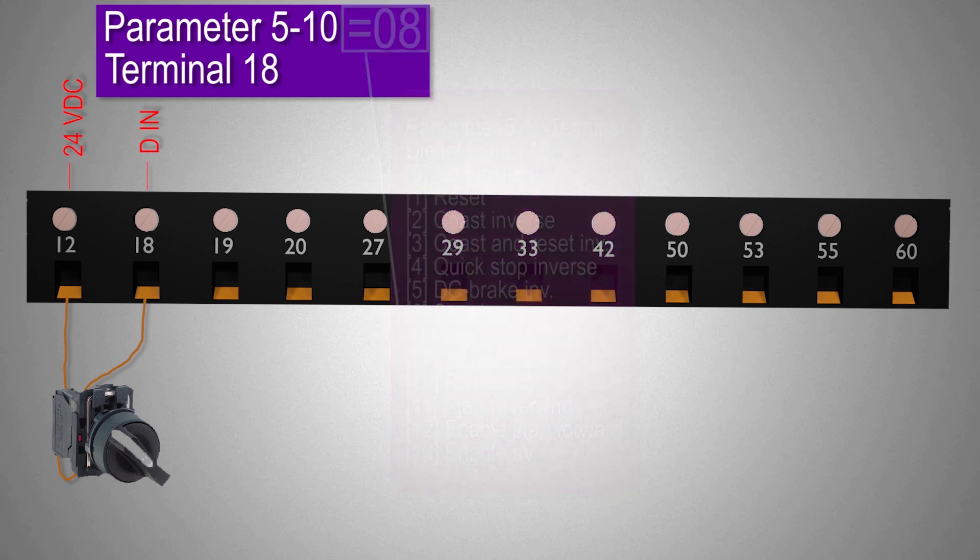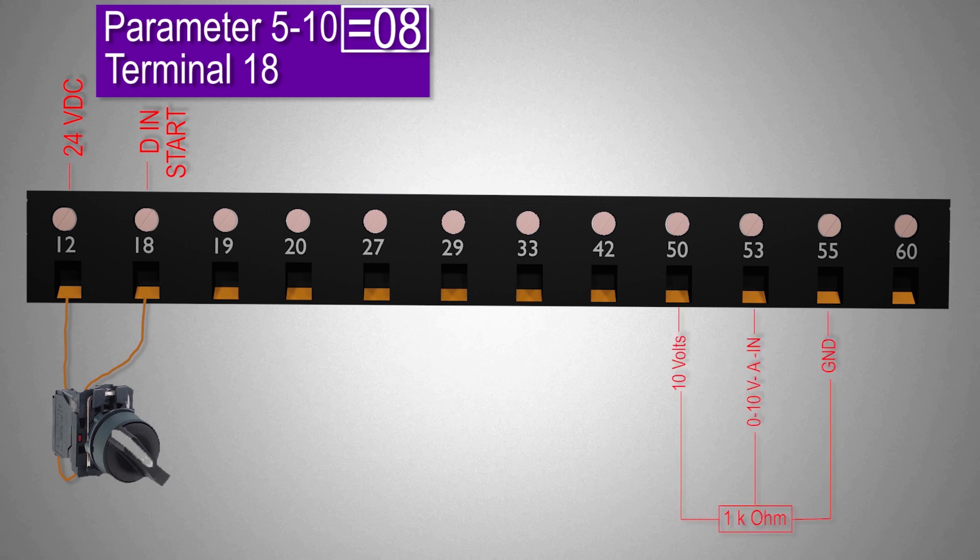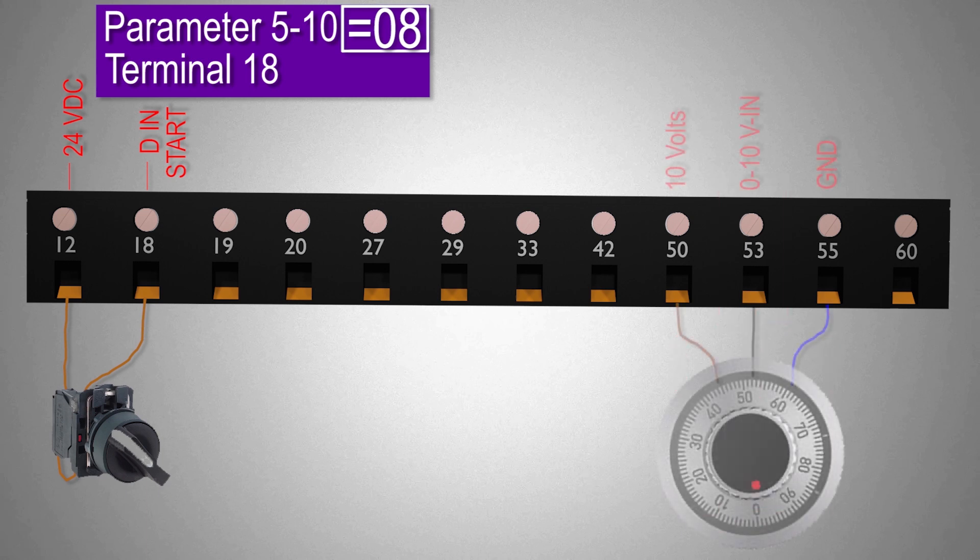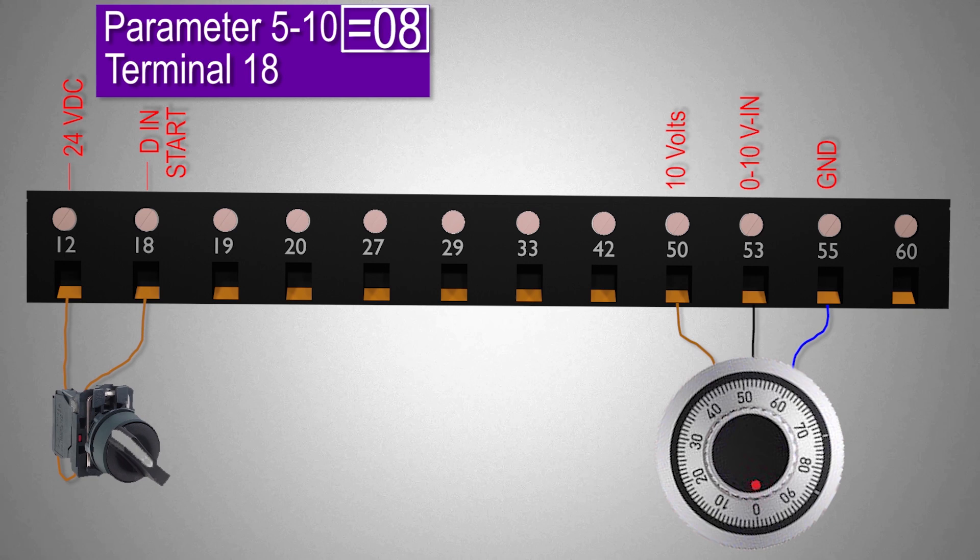Now the next thing is to connect a potentiometer at terminal 53 which is an analog input with 0 to 10 volts signal. We can connect 3 wires of the potentiometer at terminals 50, 53 and 55. Now when VFD is powered on and we rotate the potentiometer it will inject 0 to 10 volts variable signal at analog input terminal 53.